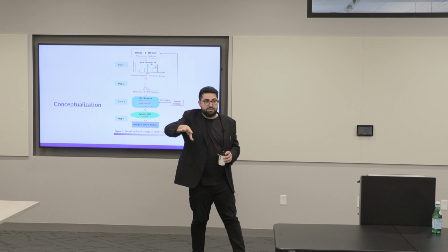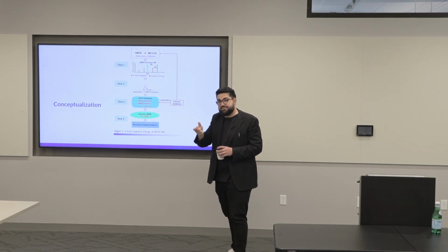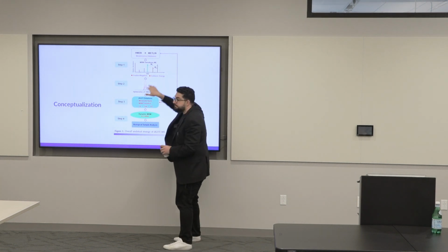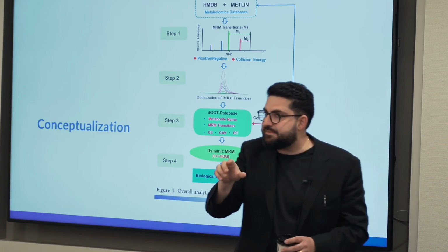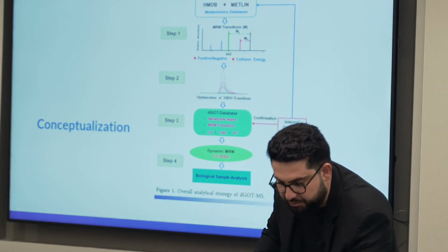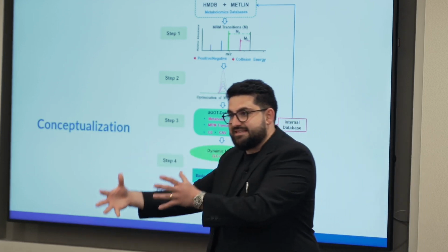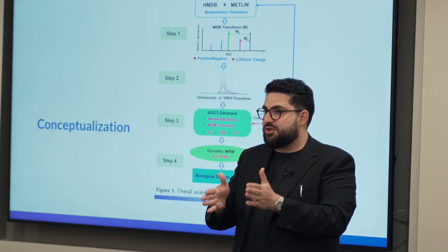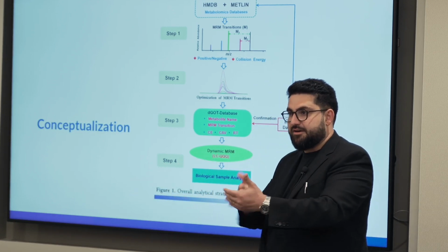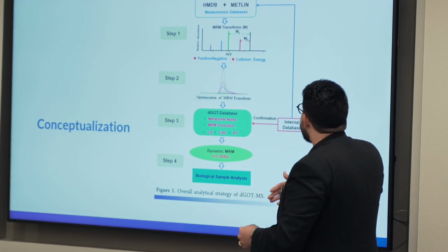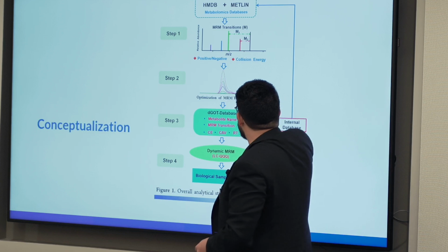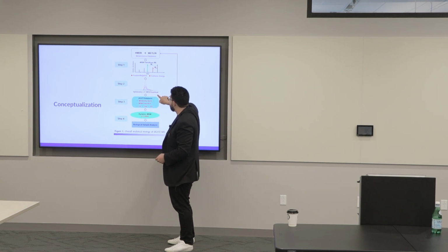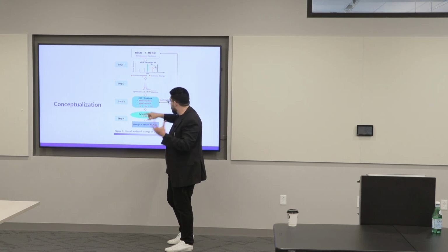In our mass spec, we only use positive ionization. With LCMS, you can use negative ionization. Positive is for nitrogen-containing compounds, and negative is usually for all the rest. And we can optimize the collision energy. We don't have that in our mass spec because it's a single quadrupole. We have one quadrupole that is filtering all these metabolites. But in an MS/MS, you have two quadrupoles back to back. They call it triple Q, but the middle Q is actually a nitrogen stream that breaks apart the molecule. So the collision energy of that nitrogen is going to be set. By optimizing these two, we're going to get optimized MRM transitions, so better, well-resolved peaks.